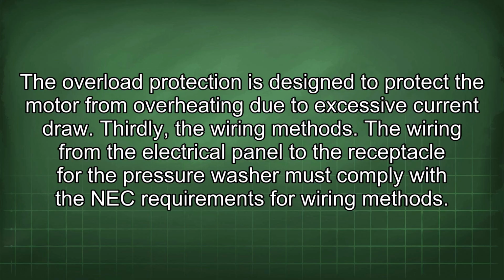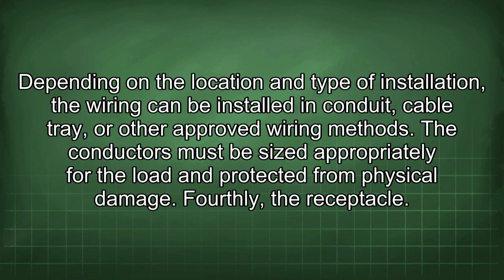Thirdly, the wiring methods. The wiring from the electrical panel to the receptacle for the pressure washer must comply with the NEC requirements for wiring methods. Depending on the location and type of installation, the wiring can be installed in conduit, cable tray, or other approved wiring methods. The conductors must be sized appropriately for the load and protected from physical damage.